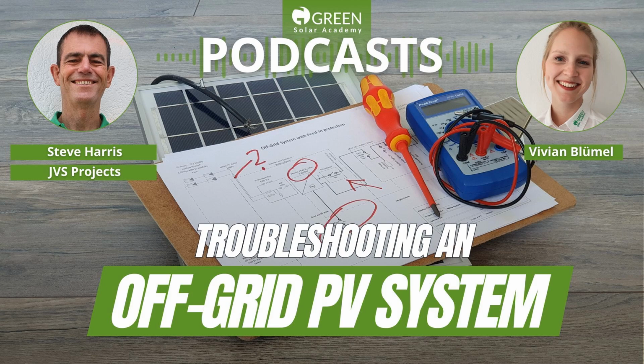One of the second things that we see is people don't even think properly about volt drop in the cables. And so they will go, oh, well, I can put 4mm cable from the string to the charge controller. But no, do the sums. If you need 6mm cable, then put it in there, because you will melt that cable. You will create a hotspot at your string fuse. You will have an issue and you will have a fire.